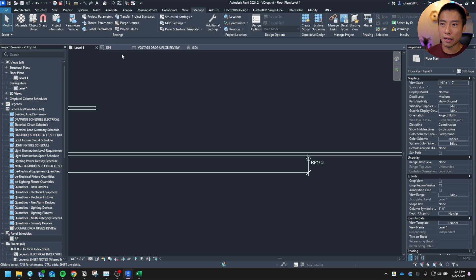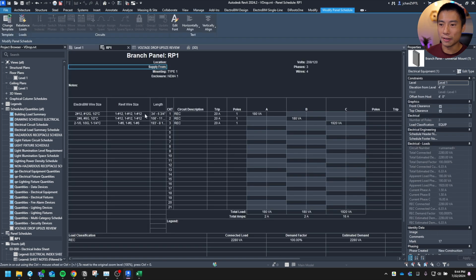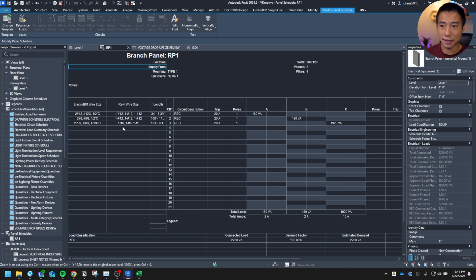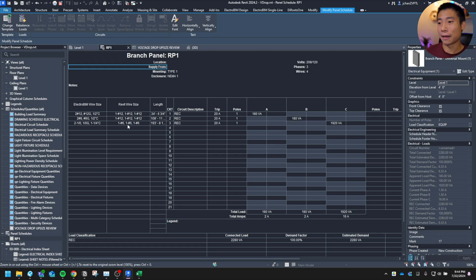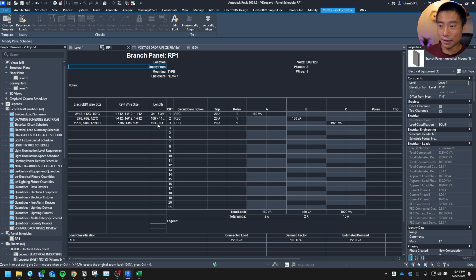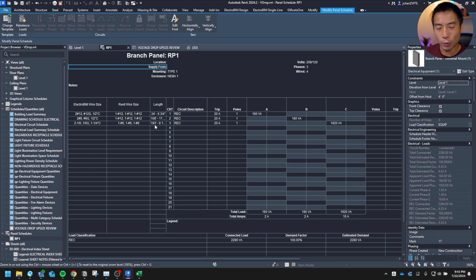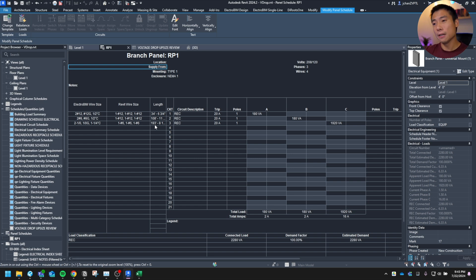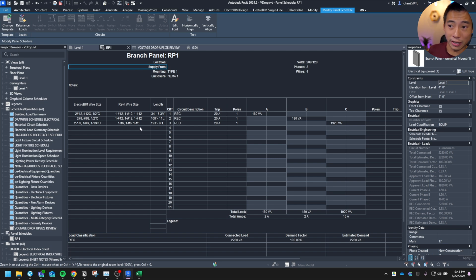But in reality, if somebody plugs in, let's say the full 16 amps of load, which will be 1920 VA. So if we hit that number, you can see that the schedule pops over to a number six. So obviously that has an impact on the size of wire that you need. And the distance is close to 200 feet. So ideally I wouldn't even run it that far. I would try to pick a closer panel.